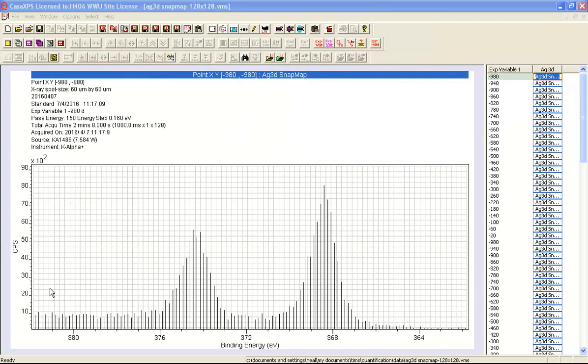Snapshot mode data represents a summation of information in the non-dispersive direction in order to calculate these intensities for each of the 128 detector channels.